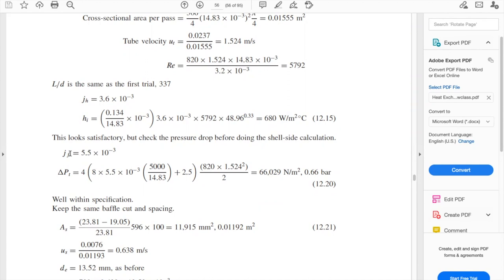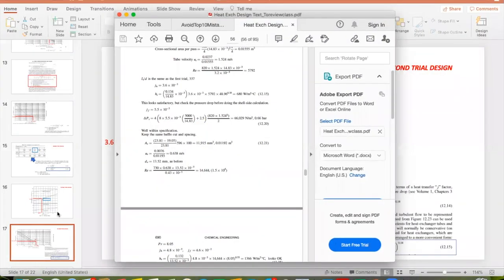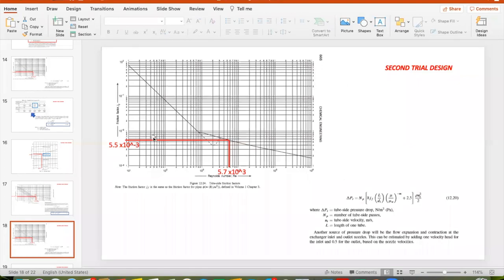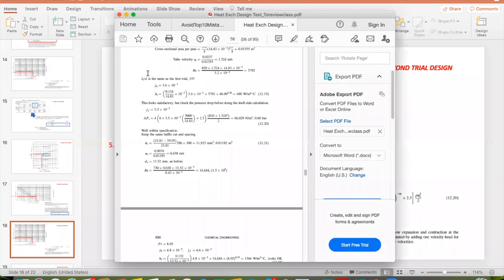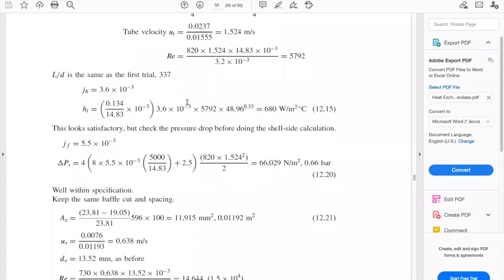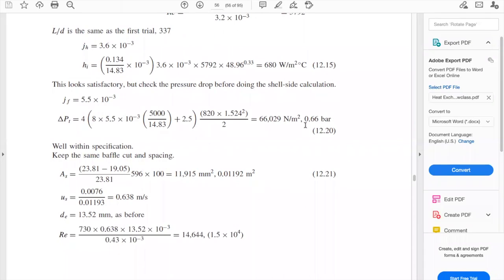We go back to figure 12.24 to get the friction factor so we can calculate the delta P in the tube side and see if we are within specification. We have all the values from our second trial design. Using the same equation 12.20, with the Reynolds number, we go to the left and get a friction factor of 5.5×10⁻³. We recalculate the delta P in the tube side and get 0.66 bars — it worked. We are within the specification of 0.8 bars permissible.